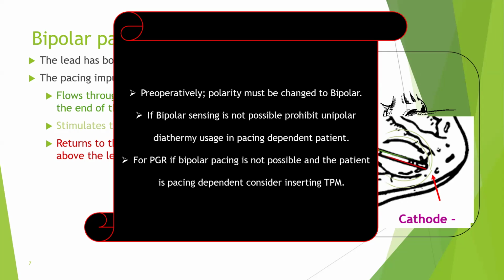But if this patient is going to go for an operation, especially if he is pacing dependent, that will risk him losing pacing during the procedure due to interference. Remember, you don't even need the diathermy. Just moving the patient around can result in myopotentials, and that could be detected by the unipolar sensing as intrinsic cardiac activity. So preoperatively, for any type of operation, you must change the polarity to bipolar.